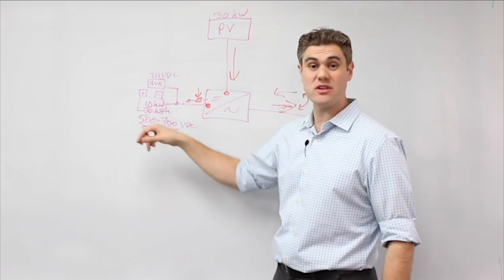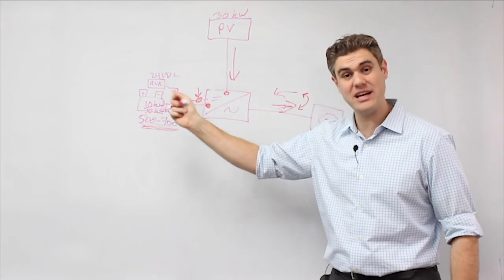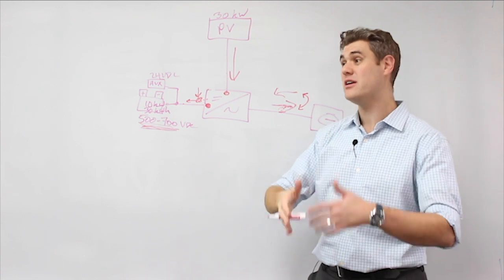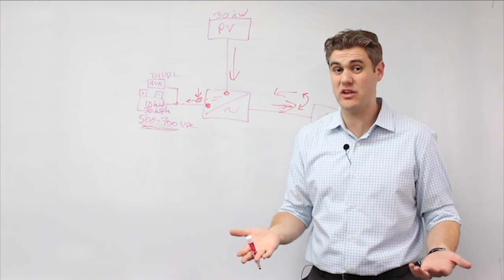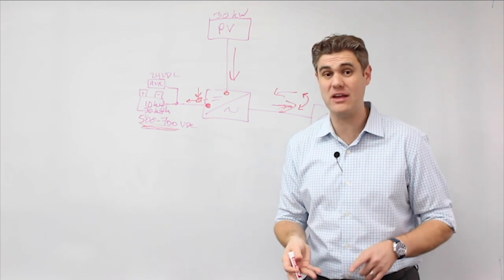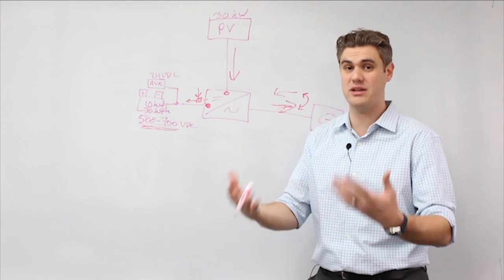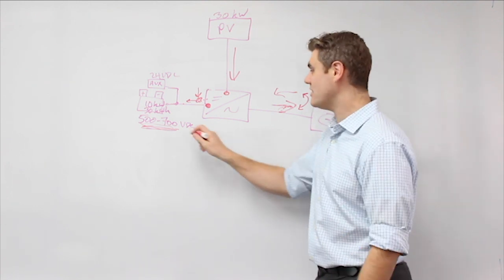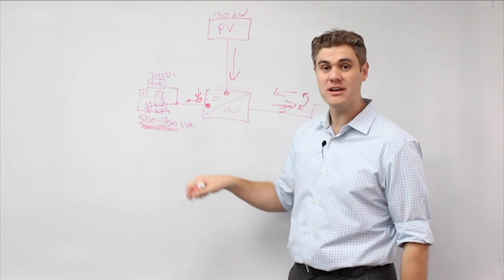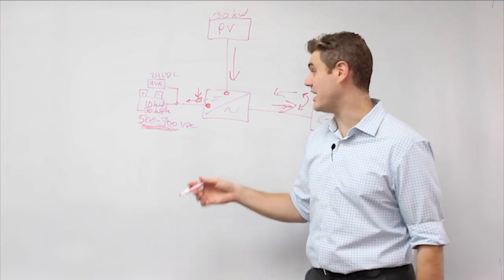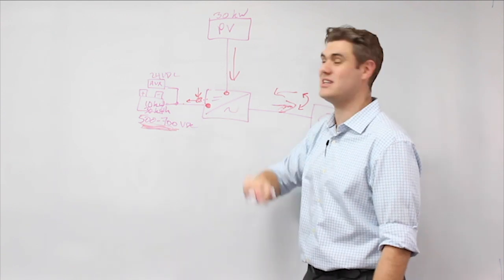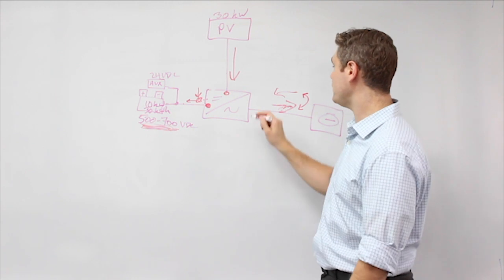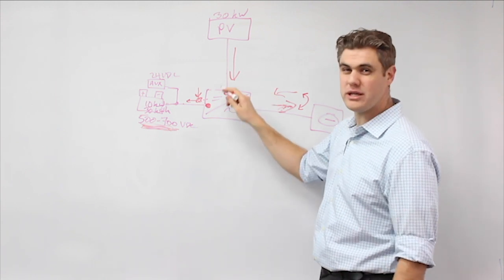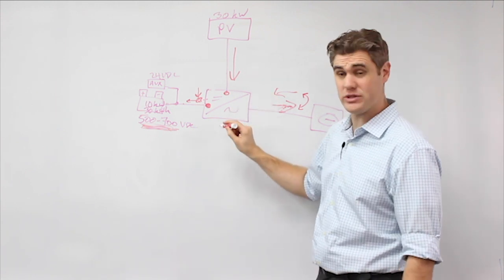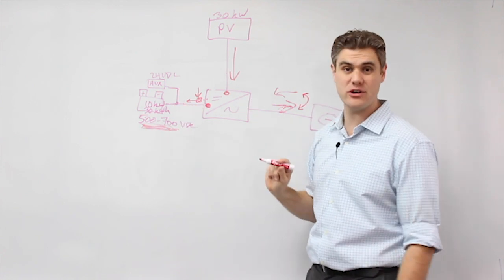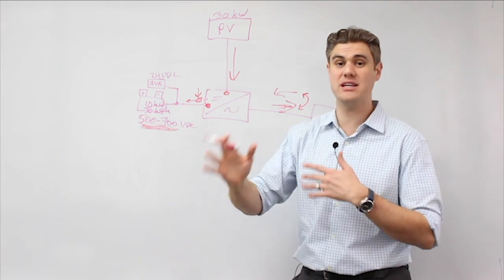think in the future this test might go away with UL 1973 or 9540, which test a variety of specs on the battery already, like current and capacity and voltage and fire safety and enclosure and NEMA ratings. I think this might actually already get covered in another existing UL standard so that this test that I'm describing doesn't need to happen twice. So in the future, it's pretty probable that only the inverter will need to be tested, not the battery and inverter together. And that'll streamline even more.